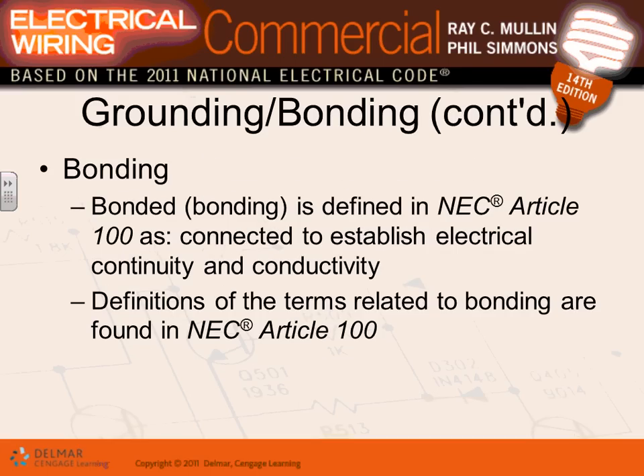So bonding, guys, puts things at the same potential. Adam, do you see the power pole coming down? Now what happened? This has to be bonded to the grid, and the grid has to be bonded to the equipment grounding conductor. Now it's carrying current, right? If this becomes energized because of something malfunctioning in the whole grid here, and Chad, you hold one hand here and one hand here. You got 0 here, 1 here. What's going to happen? The current goes right through your heart. It's a perfect shock. So that's why they bond all these power poles coming in.